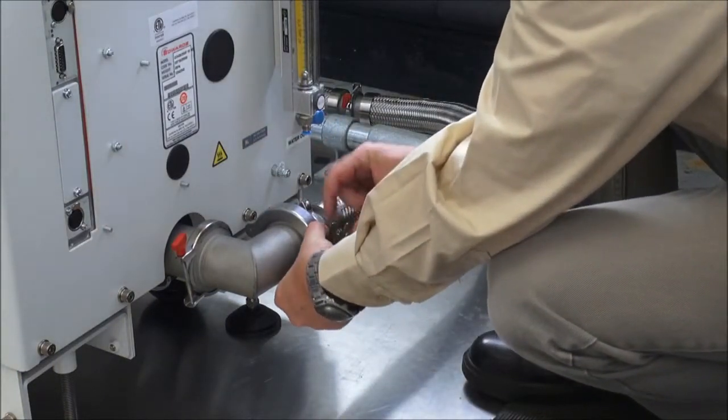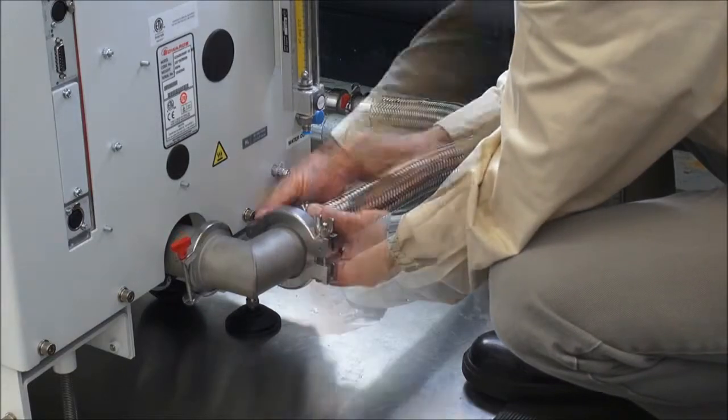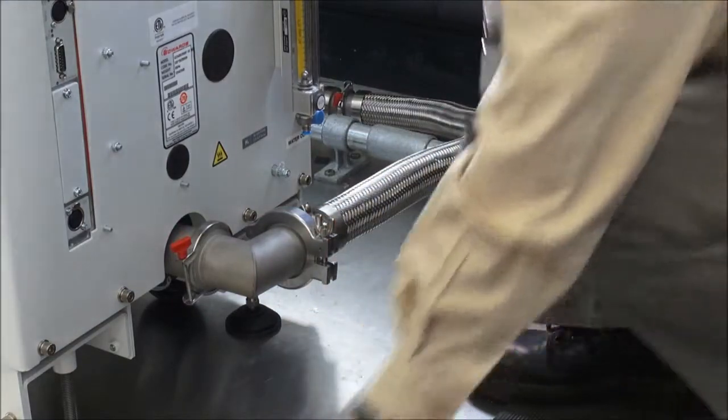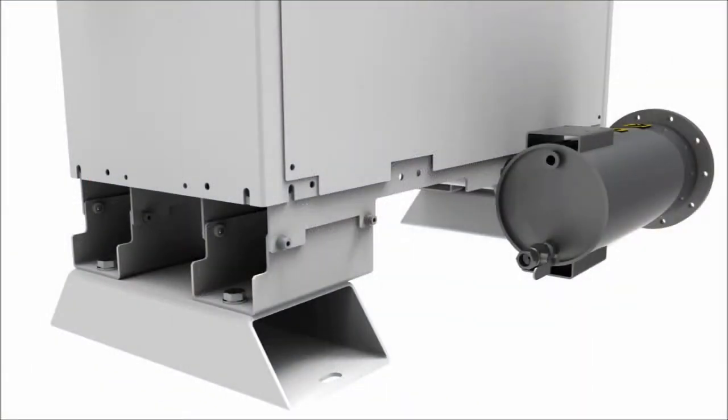Remember that condensation of moisture or volatiles can often occur, so make sure the piping drains downhill. Otherwise use a drainable accessory silencer trap to catch any expected condensates.